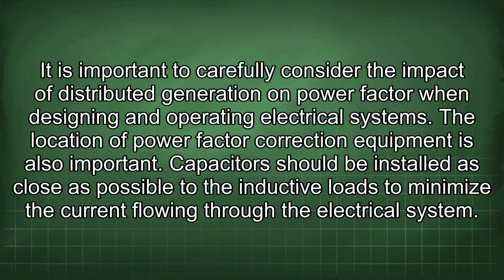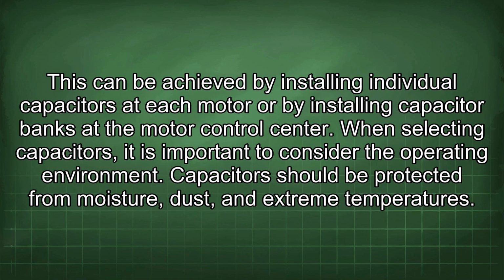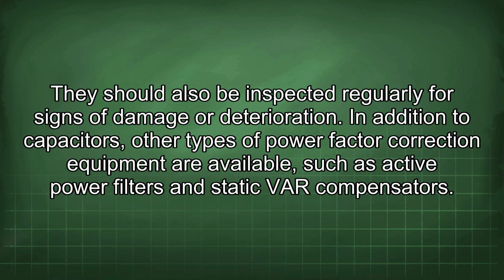The location of power factor correction equipment is also important. Capacitors should be installed as close as possible to the inductive loads to minimize the current flowing through the electrical system. This can be achieved by installing individual capacitors at each motor or by installing capacitor banks at the motor control center. When selecting capacitors, it is important to consider the operating environment. Capacitors should be protected from moisture, dust, and extreme temperatures. They should also be inspected regularly for signs of damage or deterioration.